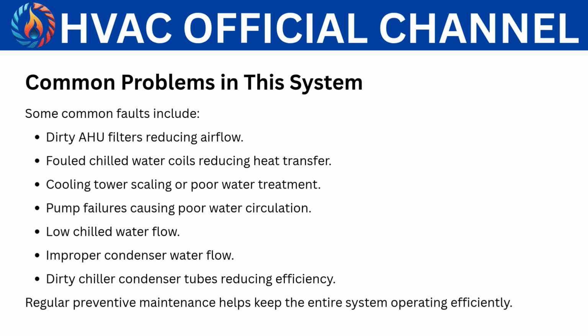Common problems in this system. Some common faults include dirty AHU filters reducing airflow, fouled chilled water coils reducing heat transfer, cooling tower scaling or poor water treatment, pump failures causing poor water circulation, low chilled water flow, improper condenser water flow, and dirty chiller condenser tubes reducing efficiency. Regular preventive maintenance helps keep the entire system operating efficiently.